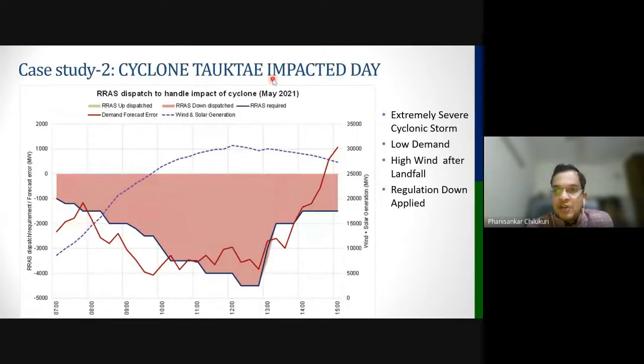Similarly, during cyclone Tauktae, an extremely severe cyclonic storm, there was low demand, and after the landfall there was high wind, obviously. We applied regulation down, looking at the demand forecast error. The demand forecast error was minus 4,000 megawatt. So we applied the RRAS down instruction to all the thermal generators and decreased generation by around 4,000 megawatt to compensate for the forecast error, because we were not expecting such high wind. And to save coal and ensure the penetration of renewables, we applied RRAS down.